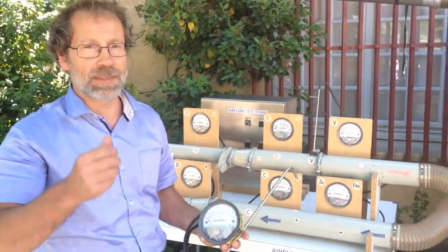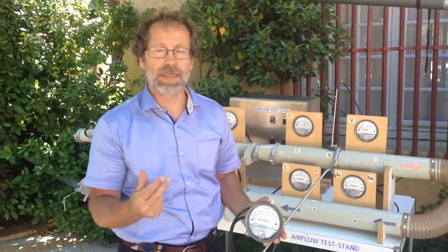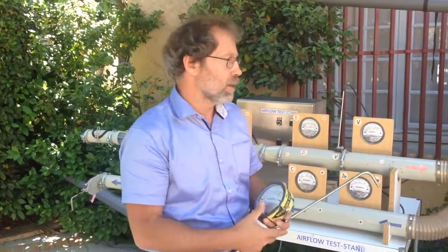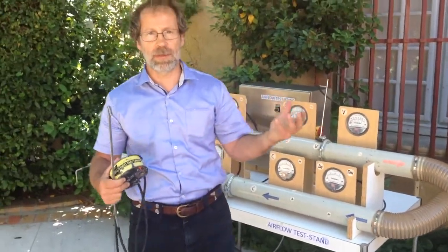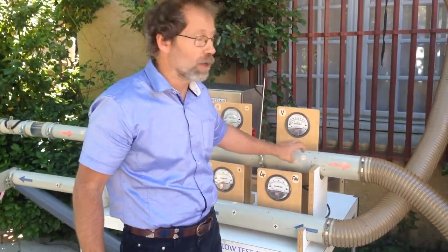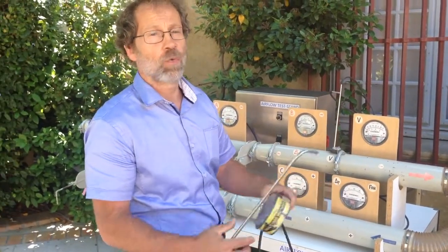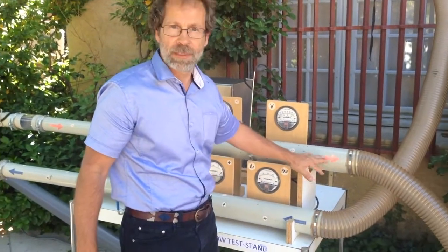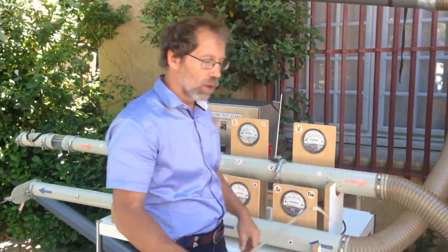Then I have a very simple instrumentation that I can use for troubleshooting to see if the air balance is stable. Am I operating at my target condition in terms of vacuum and airflow? Is it stable, or is there maybe a problem with the transportation speed, and there can be all kinds of problems. I give you some example. Maybe the duct sizing is too big, resulting in a very low transportation speed, which I can identify with the pitot tube, and the low transportation speed will result in accumulation of material inside this duct system and eventually in a blockage.